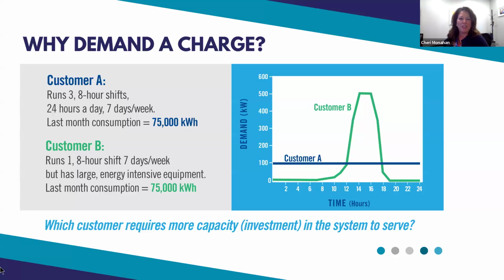For the demand charge, customer A could probably be served at a lower voltage. Customer B, who's using the system but only peaking at 500 kilowatts of demand, requires larger wires, bigger poles, more concrete. They're not utilizing the system well because they're peaking and then not using it, but we still have to put those bigger assets in place to serve them, even if it's only 30 minutes out of the whole hour that they're at that 500 kilowatt level.